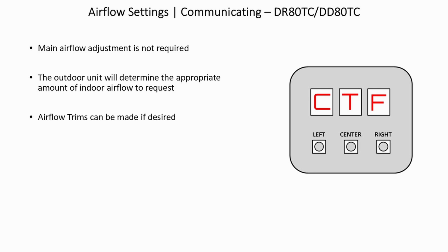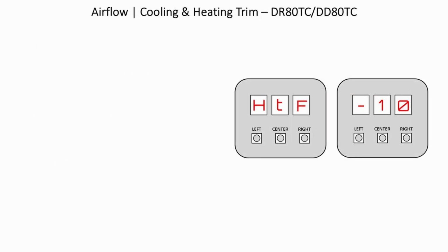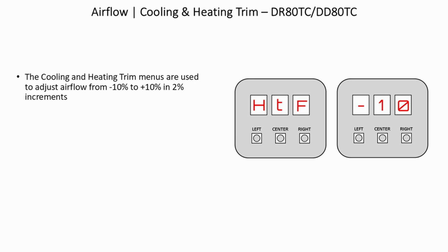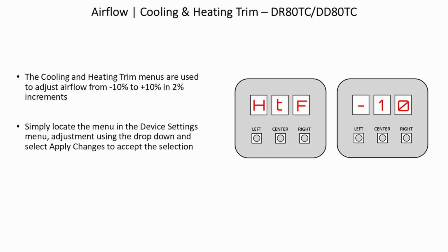Airflow trims can be made if desired. Cooling airflow profile for the indoor blower can be changed. Airflow, cooling and heating trim for the DR80TC and DD80TC. The cooling and heating trim menus are used to adjust the airflow from -10 to +10% in 2% increments. Simply locate the menu in the Device Settings menu, adjust using the drop-down, and select Apply Changes to accept the selection.